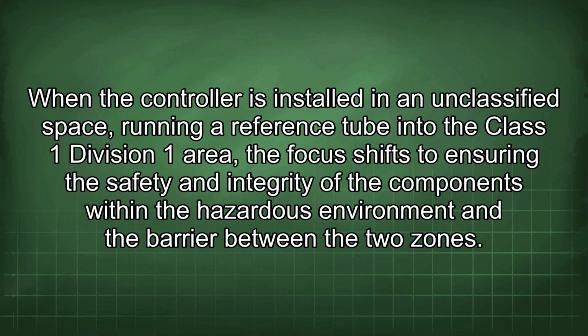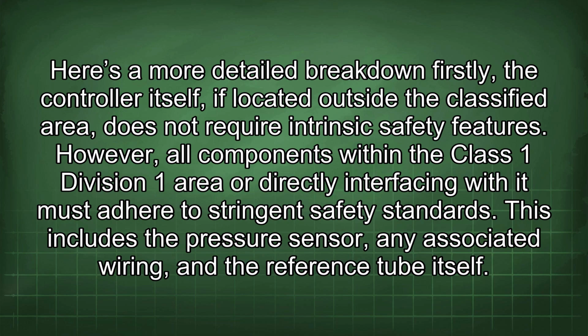When the controller is installed in an unclassified space, running a reference tube into the Class 1 Division 1 area, the focus shifts to ensuring the safety and integrity of the components within the hazardous environment and the barrier between the two zones. Here's a more detailed breakdown. Firstly, the controller itself, if located outside the classified area, does not require intrinsic safety features. However, all components within the Class 1 Division 1 area or directly interfacing with it must adhere to stringent safety standards. This includes the pressure sensor, any associated wiring, and the reference tube itself.